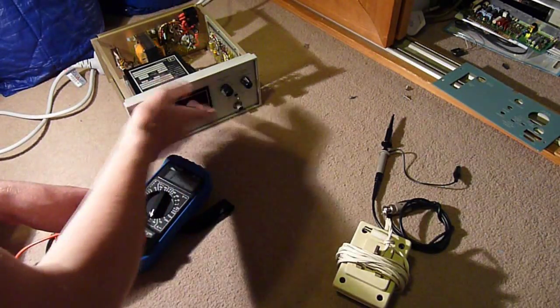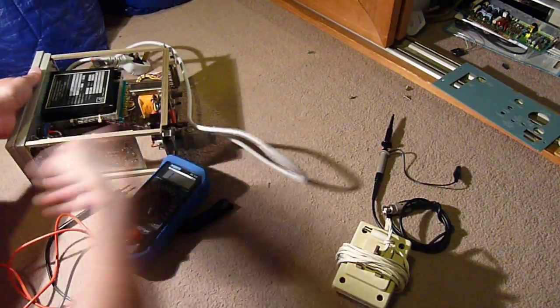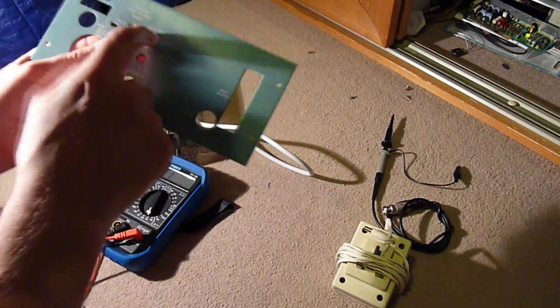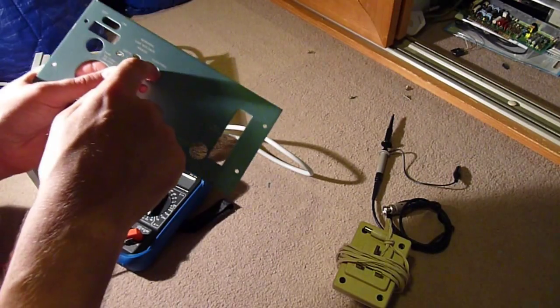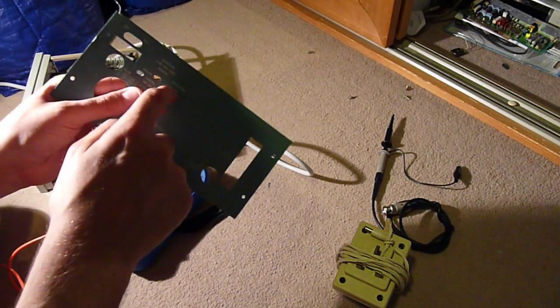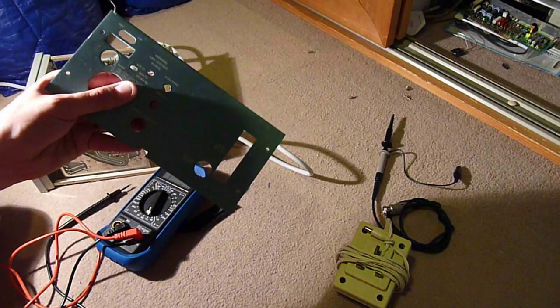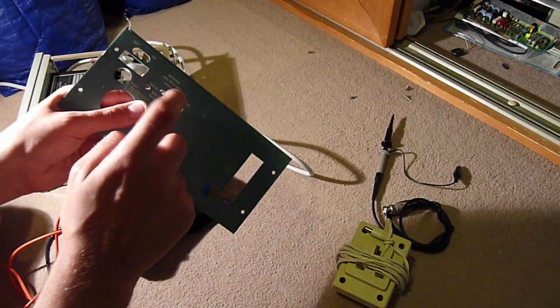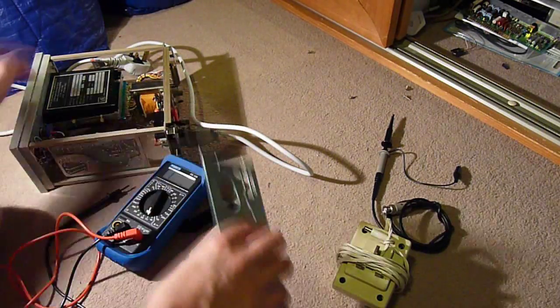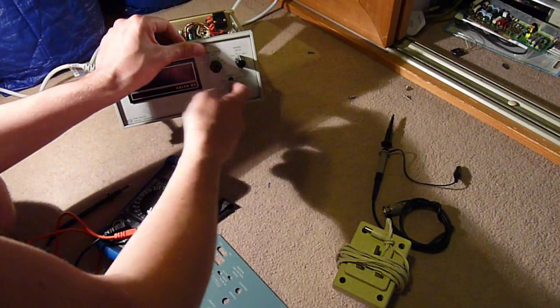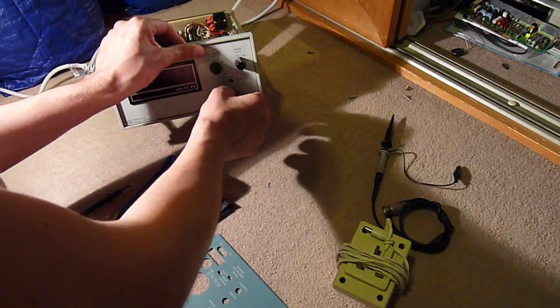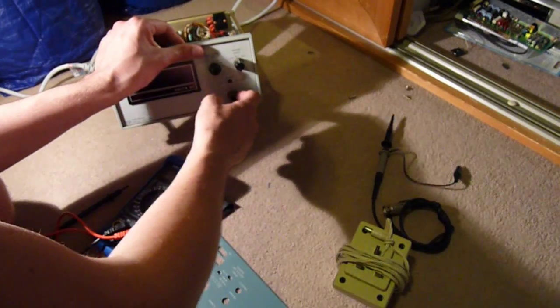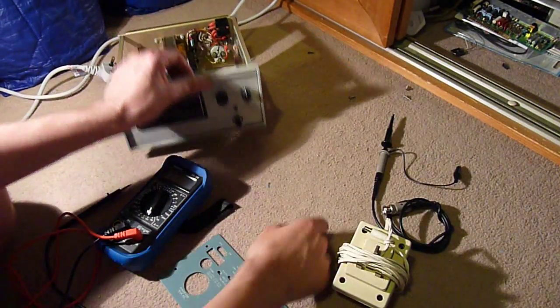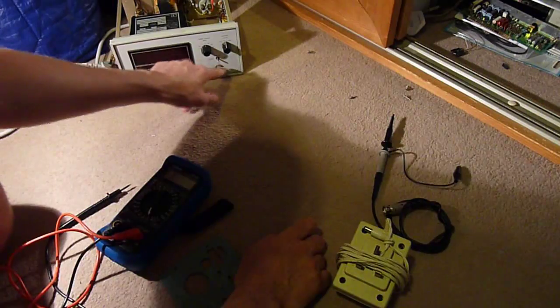And the same goes with something like this. Although this does have a floating and ground switch, so if you do measure a mains potential with this that isn't isolated from mains, such equipment, make sure the switch is not set to ground position, because the ground floating literally disconnects the negative of this. If you knock it to floating, it disconnects this from mains earth. Knocking it to ground connects it to mains earth. Make sure that is not connected to mains earth, basically.